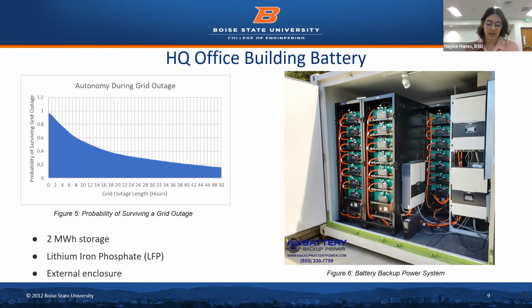The team decided to install the batteries in an external enclosure next to the HQ office building as a safety measure to prevent a fire from extending to the building in the event of a thermal runaway. This container will be placed in close proximity to the outside of the HQ building. Its specific location is flexible and can be left up to Lake Nona Town Center, due to the building being under construction and the lack of information on the space available for the pre-built system.